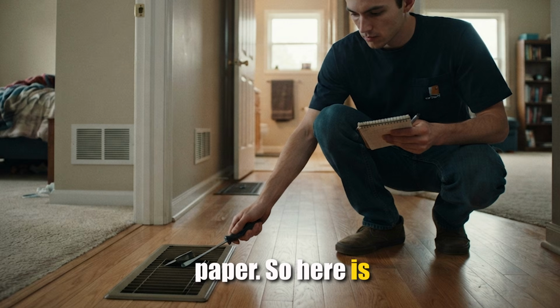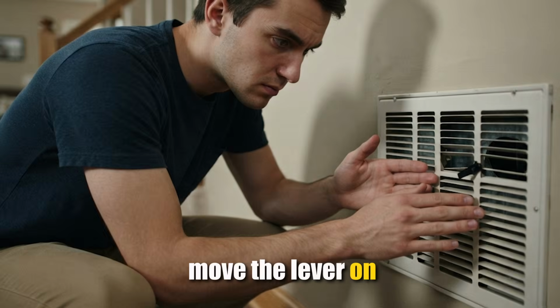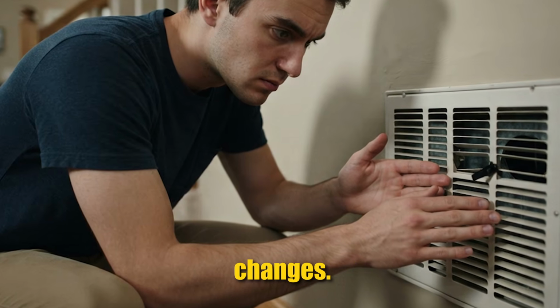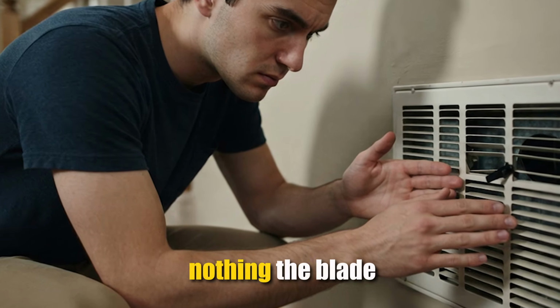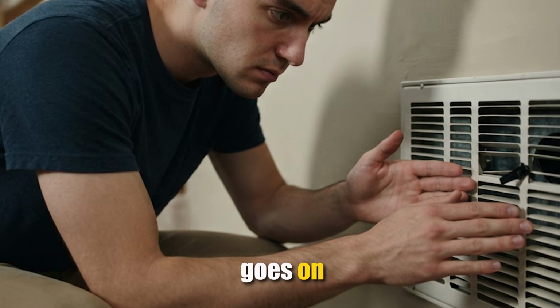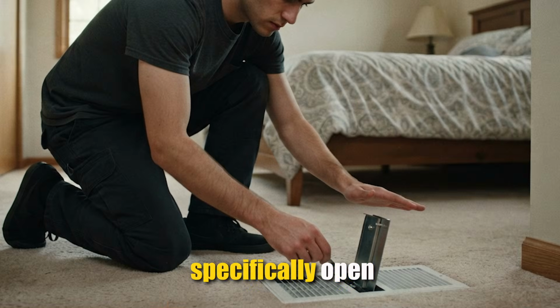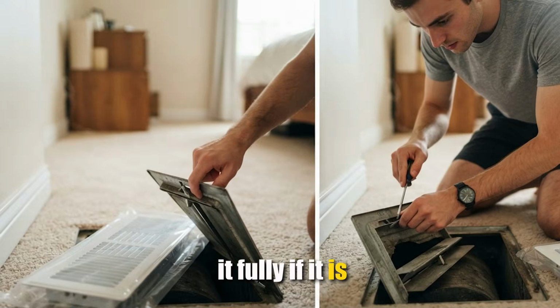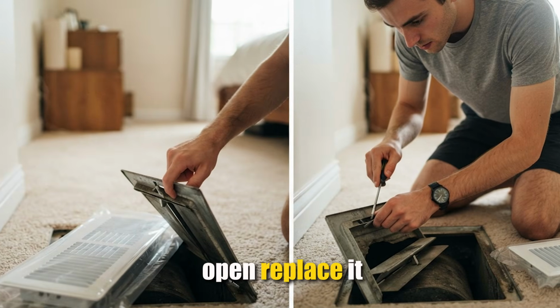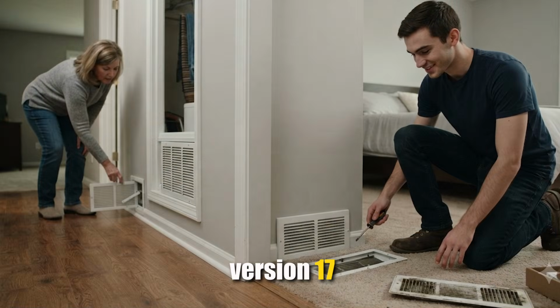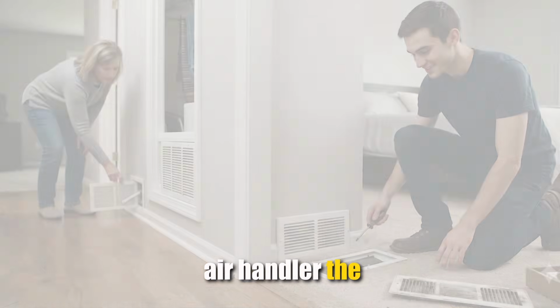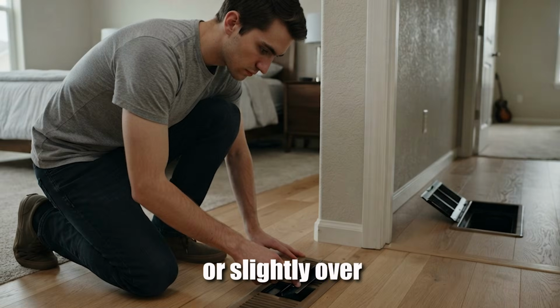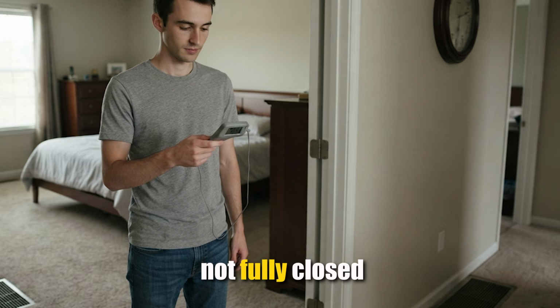So here is what I want you to do this week. Walk through your house and test every register damper. Move the lever on each one and feel whether the airflow actually changes. Any register where moving the lever does nothing, the blade is not responding, goes on your list. Then go to your hot room register specifically. Open it fully. If it is broken and stuck at anything less than full open, replace it with a high flow version. $17, 4 minutes. Then partially close the dampers in the rooms closest to your air handler. The ones that are already comfortable or slightly overcooled, 50%. Not fully closed. Then wait one full cycle and measure.